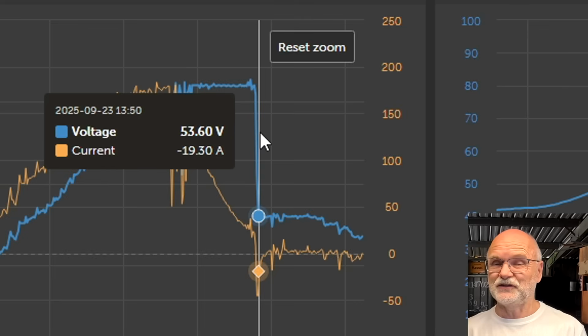Throttled down to 53.6 volts, which is 3.35 per cell, and we are floating the battery now. When we say floating, we don't mean floating the battery like we used to with lead acid batteries in the past. When we reduce the voltage to 3.35 volts, there will be no current going into the battery anymore - this is exactly the same as turning off your charger. But floating the batteries at 3.35 volts has the big advantage that it keeps the battery at 100% as long as you have enough solar to power your loads.